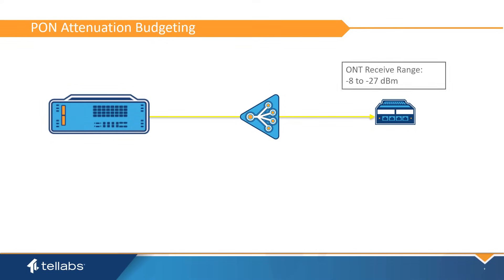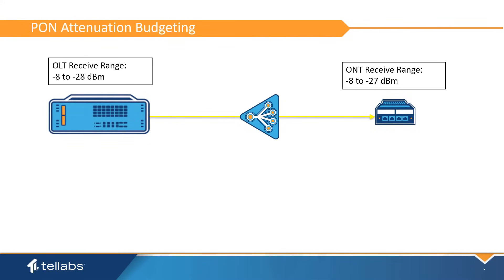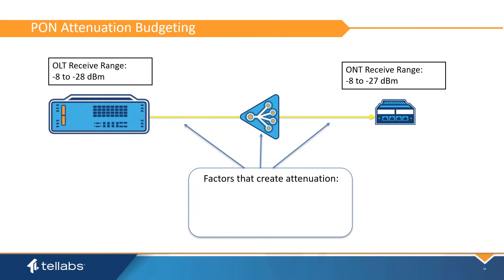Equipment standards for PON establish the fiber signal receive range for the ONT and OLT transceivers. This is between -8 and -27 dBm downstream and -8 to -28 dBm upstream. Since the optical LAN system is passive on the ODN, care must be taken to ensure that the planned deployment creates adequate attenuation so that the measured fiber signal falls within this range. Factors that create attenuation include the optical splitter, the distance between the OLT and ONT, fiber connectors, and splices. An understanding of the insertion loss created by these elements is critical to establishing a usable plan.